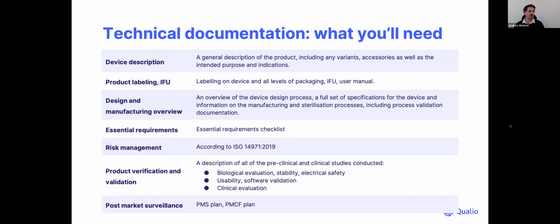Then there's also a requirement to have information about risk. Usually the risk management file, best to have it in accordance with the standard on risk management, ISO 14971, the 2019 version. And then the sections on product verification and validation, usually the bigger section here, which can cover quite a few different areas, like some of the examples we've got: biological evaluation to ISO 10993, stability testing, electrical safety testing to IEC 60601, and so on. You've got specifics like usability, software validation if your device has software, and one of the most critical parts of this section is the clinical evaluation. I'll go into that more in the next slide.